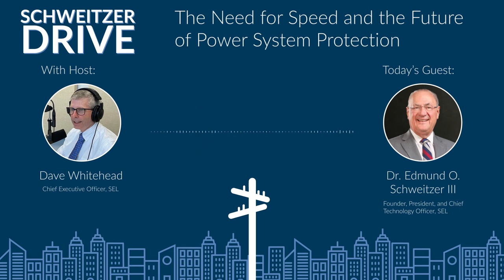Well, let's see, where did we start here, Dave? We started with a circuit breaker, say, at two or three cycles, and a relay at one or two, and now we're down to, say, 1 or 2 milliseconds for a relay, making its operating time nil compared to the circuit breaker. So we've really sped the overall clearing process up by taking a third off of the total time, say. But you start to think about it. Now, what are the breaker guys doing?